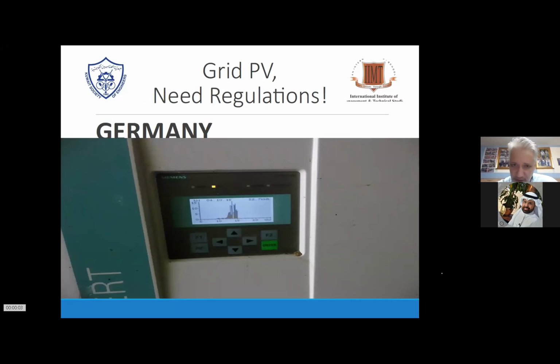Here, for example, that was a 300 kilowatt system per farm stall. They always had trips between 11 and 12 and between 12 and 1 o'clock. So what happened was actually one of the phases of these inverters caused an interruption and some transients, and it caused the phase to vibrate more or less. So the other inverters picked that up and switched off. So during this cascading effect, more and more inverters switched off, because the next inverter made the same measurements.